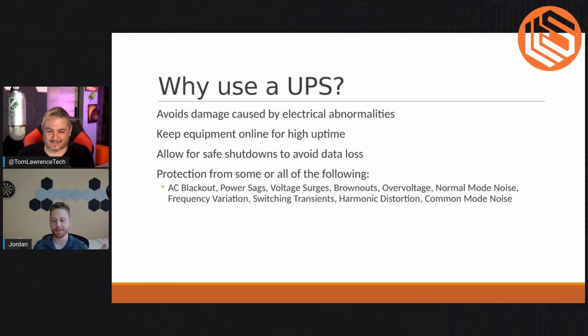Let's go over some of the most common types of utility failure. Blackout is the most famous — that's when you lose power and stuff shuts down. There are 10 common power issues. Power sag is where your voltage drops below sufficient voltage for your equipment — say from 120 volts down to 103 volts, and some equipment can get upset. Power sag is a short-term thing. Brownout is an extended power sag. Voltage surges are where your input voltage goes way too high.